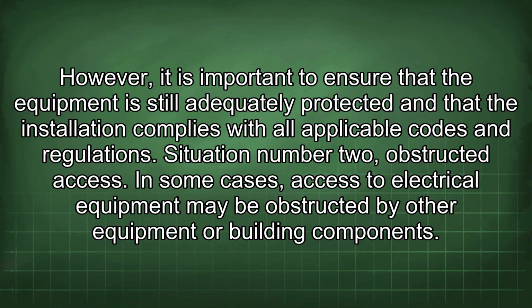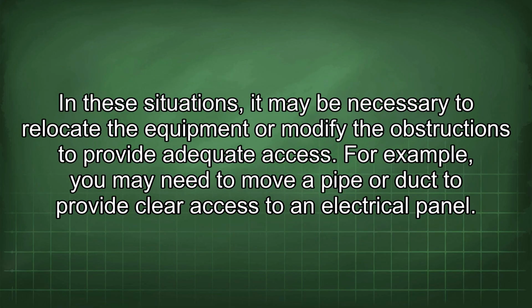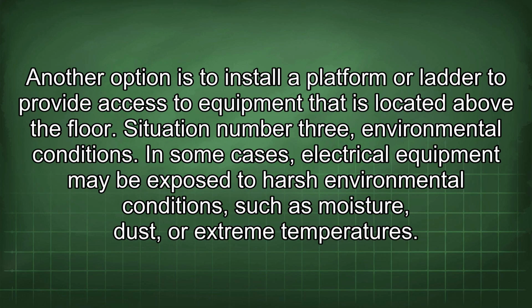Situation number 2: obstructed access. In some cases, access to electrical equipment may be obstructed by other equipment or building components. In these situations, it may be necessary to relocate the equipment or modify the obstructions to provide adequate access. For example, you may need to move a pipe or duct to provide clear access to an electrical panel. Another option is to install a platform or a ladder to provide access to equipment that is located above the floor.